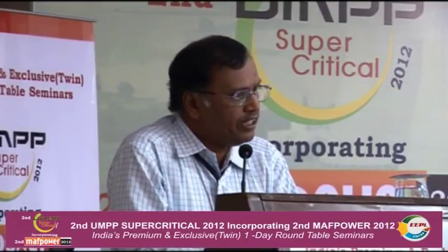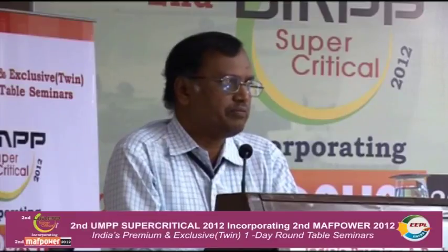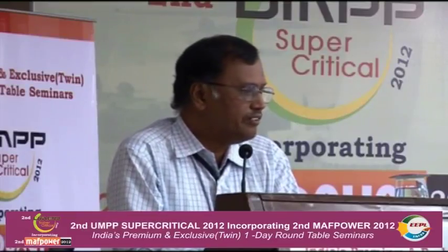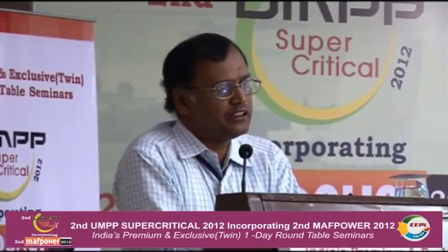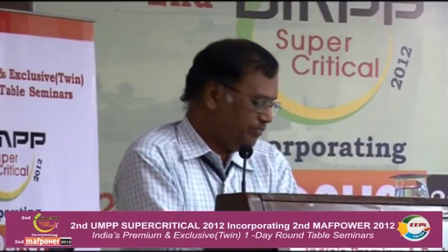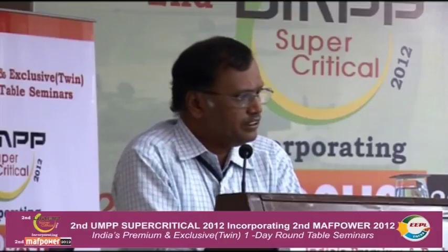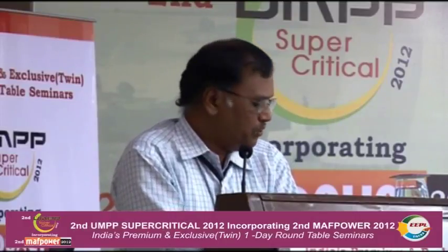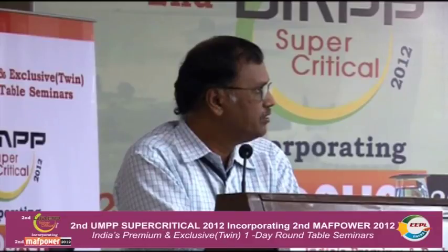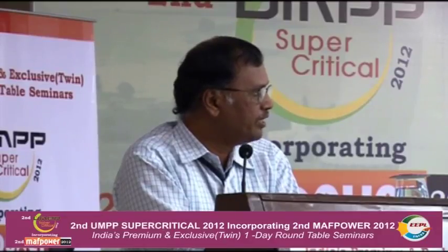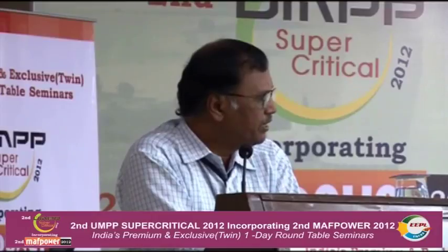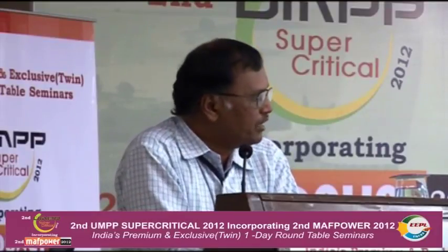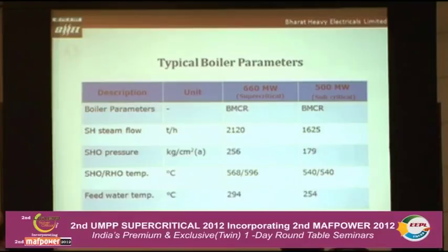If you compare with the typical 500 megawatt, I will say 500 megawatt is the backbone because more than 100 sets are in operation, and the first set has crossed more than 25 years. So pressure-wise, it has gone from 170 ata to 250 ata. That means an 80 gauge increase. From the boiler side it is 179 to 256. Similarly, the superheater temperature has also gone up from 540, 542 to 568, 596. The standardized superheater temperature is 568. Because of the lower pressure, we can go to a slightly higher reheat temperature of 596.